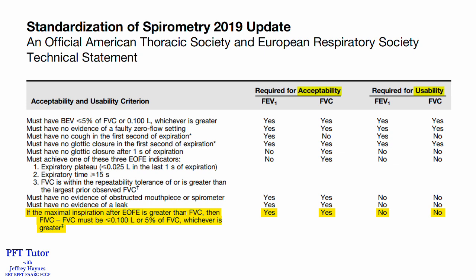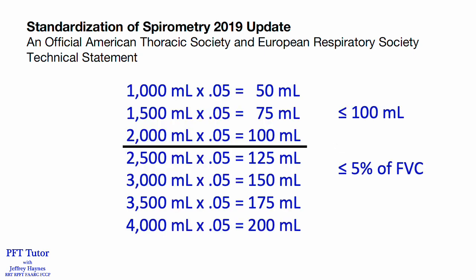If this is not achieved, the test may be deemed as usable, but not acceptable. In other words, if the forced vital capacity is 2 liters or less, the 100 mL criteria apply. But for forced vital capacities greater than 2 liters, the 5% rule applies. So as the forced vital capacity gets larger, the acceptable gap between inspired and expired volumes also increases. For example, if the forced vital capacity is 4 liters, a gap of up to 200 mLs is considered acceptable.